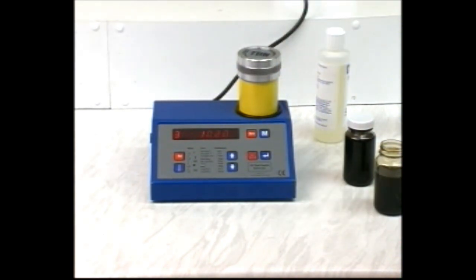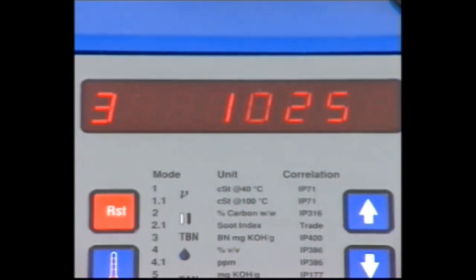The unit will now display the reference value for the new oil which will be used for testing used samples of this batch of oil, so record it in your log book.